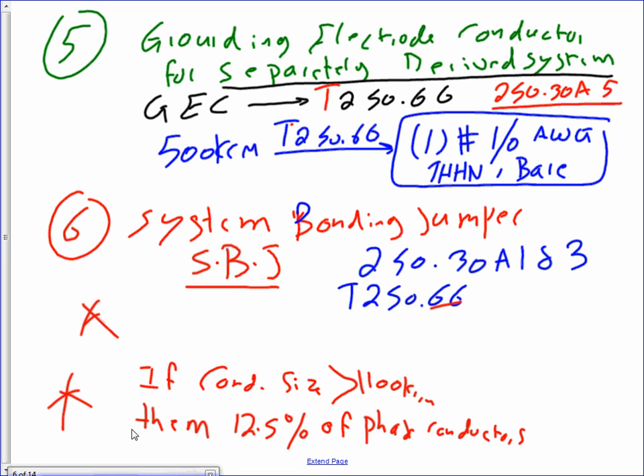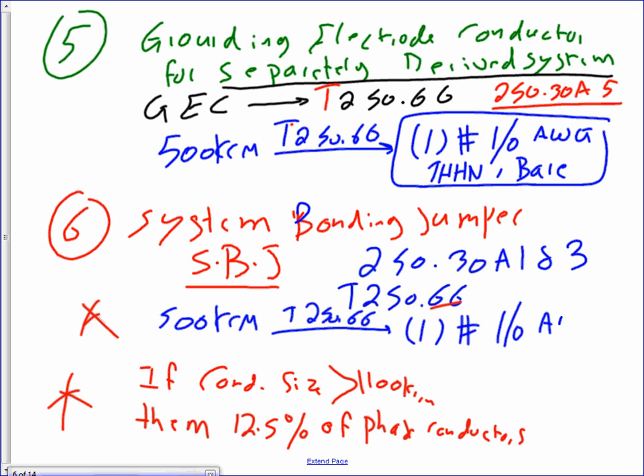Okay, gentlemen. So for the main bonding jumper, same calculation here. You take the 500 kcmil, take it to Table 250.66, and that will get you a number 1/0 AWG conductor. That could be THHN or whatever.